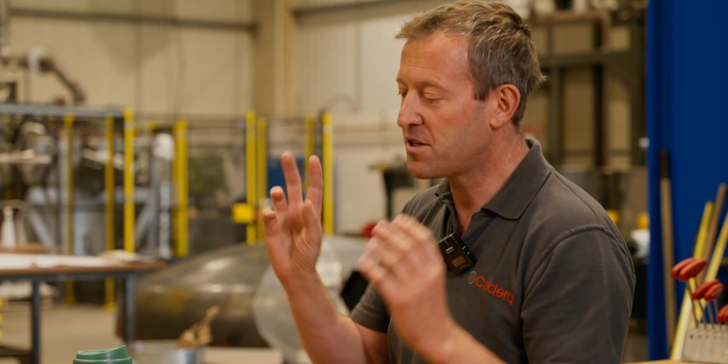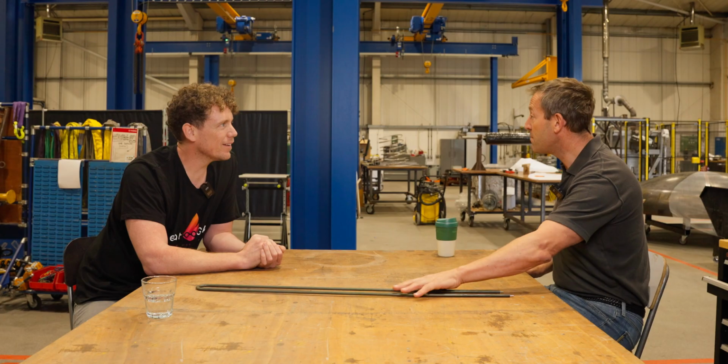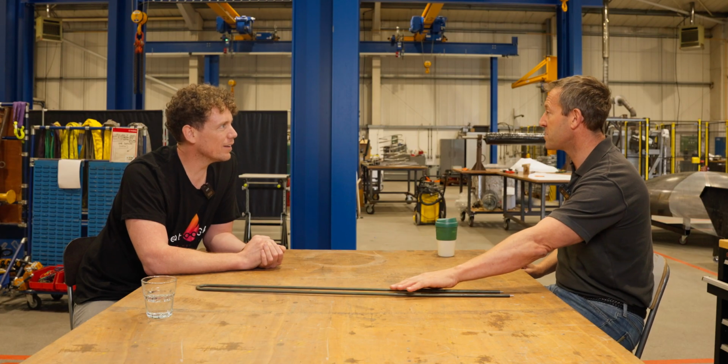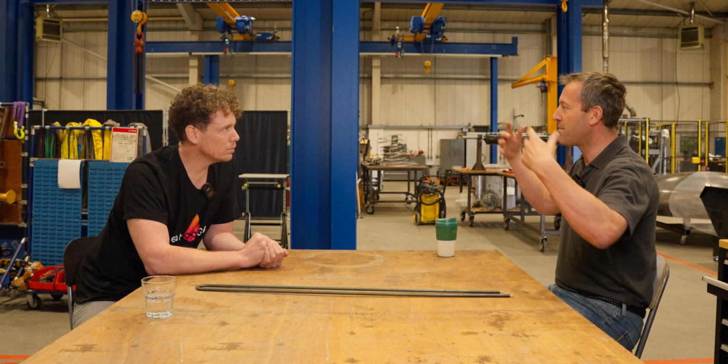Two things we do within the block: we put electric elements, little elements like this, and they're embedded, and because the aluminium is so conductive, it keeps them relatively cold. There's almost no difference between the block temperature and these elements. In most applications, the elements are much, much hotter because they only have air around them. Of course. And second, we put a little steel pipe inside it, and that's how we get the heat out, by squirting water in. So you end up with a block with electric elements, steel pipe, and aluminium and rock.